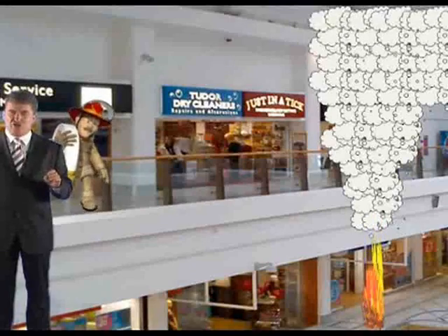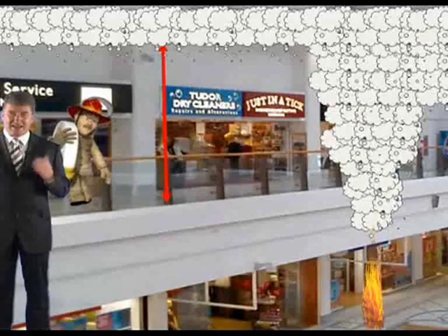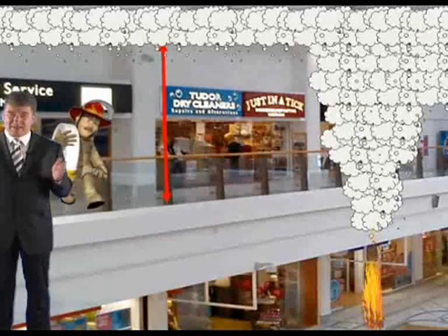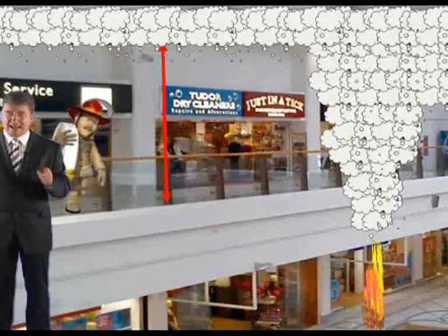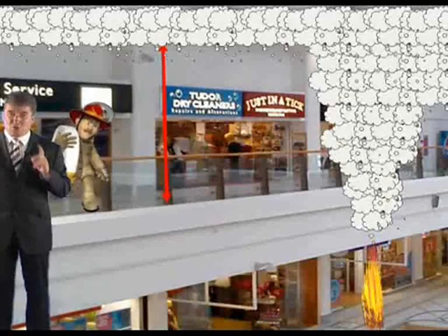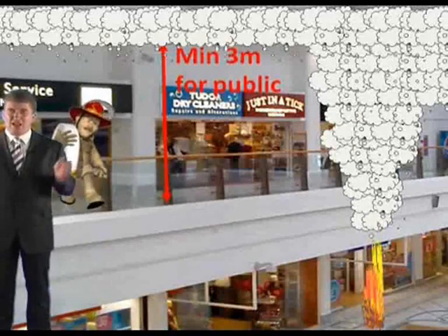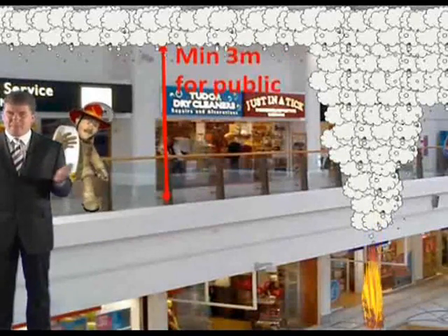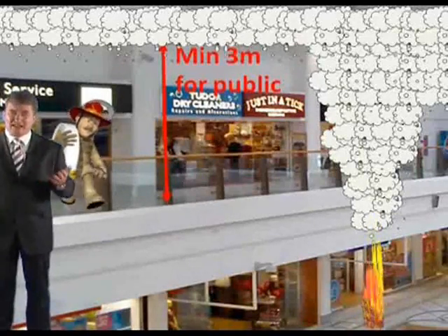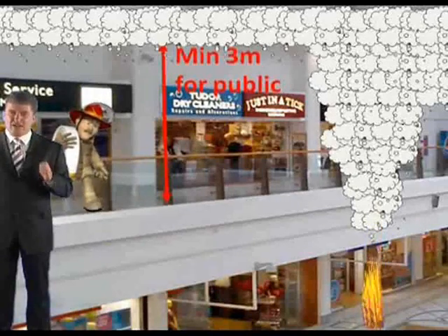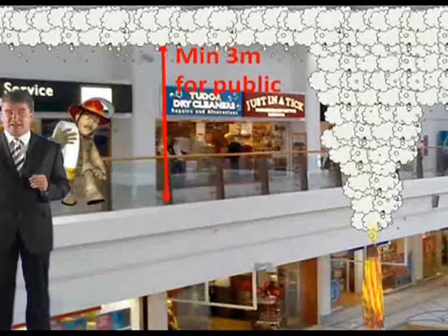For now, we're going to concentrate on the stable smoke layer of known thickness. Now, as stated, the designer needs to decide how thick the smoke layer can be allowed to become. And what do they need to consider? Well, first of all, they need to consider that smoke must be kept at a safe height above people who may be escaping beneath it. And normally the height we look at is 3 metres for members of the public and 2.5 metres for members of staff. Now, members of the public may be slower to react to the fire situation, they may be less mobile than the staff, and may require extra reassurance, and that's why they need an extra clear layer height. That's why they're given 3 metres rather than 2.5 metres.